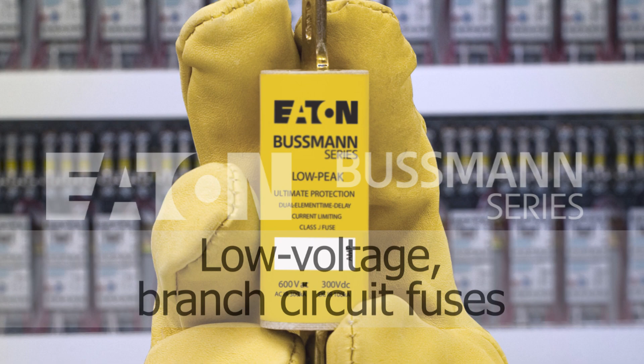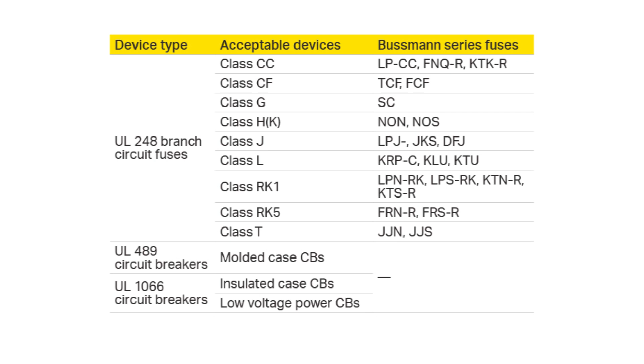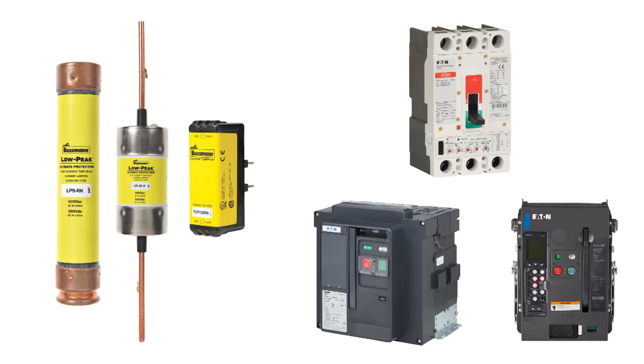The National Electrical Code defines a branch circuit overcurrent protective device as one that is capable of providing protection for service, feeder, and branch circuits and equipment over the full range of overcurrents between its rated current and its interrupting rating. They are also the only overcurrent protective devices the NEC permits to be installed in a building's electrical system. In addition, such devices must have interrupting ratings appropriate for their intended use, but no less than 5,000 amps. Branch circuit devices can protect branch and feeder circuits and service conductors at any point in the electrical system. In addition, the interrupting rating must also comply with Article 110.9.